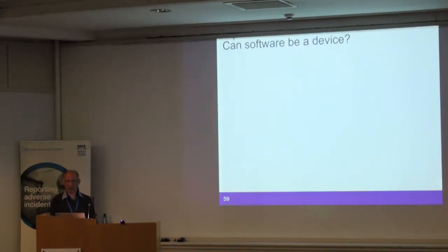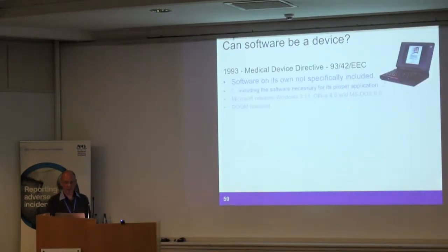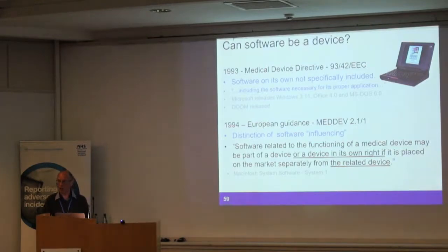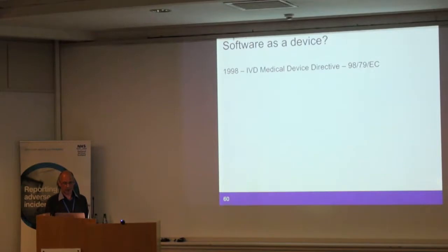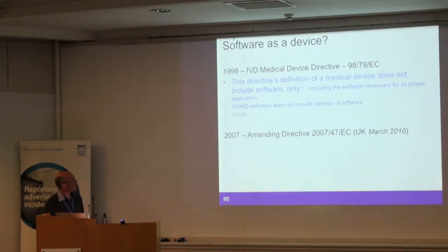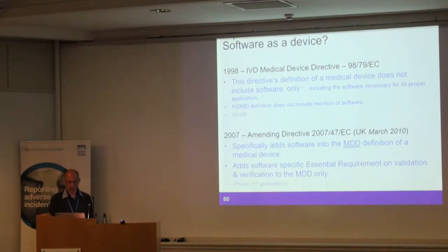But can software really be a device? Back in 1993, not really. It was part of the device. In 1994, we had some guidance from Europe saying, well, if it's part of a system, it helps the function of a device, it influences the device, yes, it can. In 1998, there were some updates: for IVDs, software isn't included in the definition of an IVD. Up to 2007, there was an amending directive for medical devices, and it specifically added software into the definition. It also added some software-specific essential requirements for validation and verification, but that was for medical devices only.